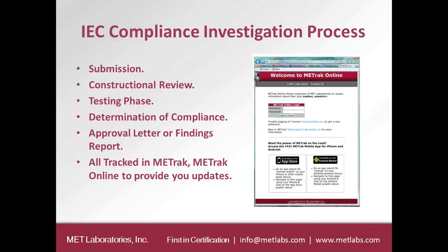Compliance investigation is basically the review of the product against the safety standard. It starts with a construction review - we look at the construction, check warnings and markings, ratings, openings in the enclosure, and check component materials and suitability. Based upon that, we come up with a test plan of anything we believe needs to be tested, and it goes through that process.